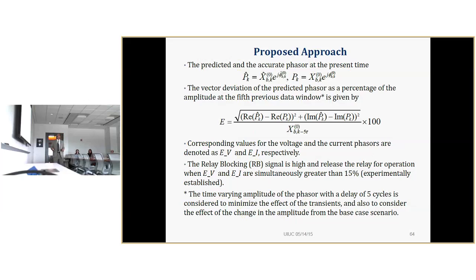So we use the second and first derivative to construct the predicted phasor in advance, and then the current value, which we took actually 5 cycles away. What is the change it has given? If that is significant, then we say that there is some fault. If that is not significant, then we say that it is not really a fault. So just to distinguish between fault and no fault scenario, this signal has been used. So this matrix has been used, and some thresholds have been worked out experimentally.